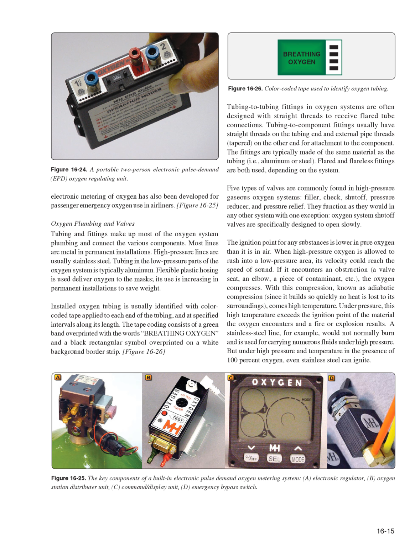Five types of valves are commonly found in high-pressure gaseous oxygen systems: filler, check, shutoff, pressure reducer, and pressure relief. They function as they would in any other system with one exception: oxygen system shutoff valves are specifically designed to open slowly. The ignition point for any substance is lower in pure oxygen than it is in air. When high-pressure oxygen is allowed to rush into a low-pressure area, its velocity could reach the speed of sound. If it encounters an obstruction, a valve seat, an elbow, a piece of contaminant, etc., the oxygen compresses.